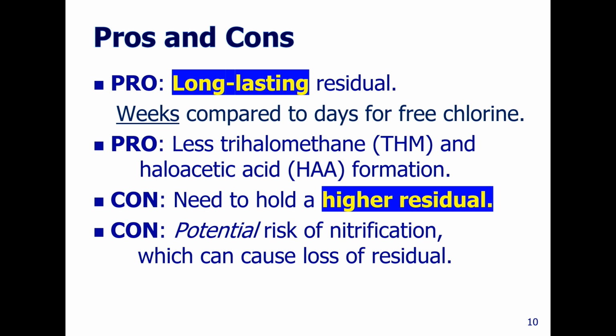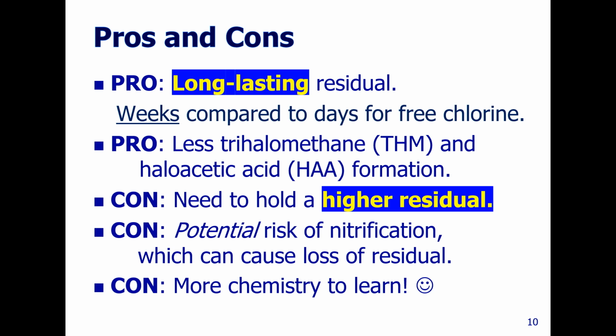The biggest problem with the chloramines is there's this potential issue with nitrification, that there's this biological process that can happen in a chloraminated system that doesn't happen in a free chlorine system. And that can cause loss of residual, which is really undesirable. But of course, the big con is you have to learn a little bit more chemistry. Now, some of us like that stuff, but some of us are kind of aggravated by that.